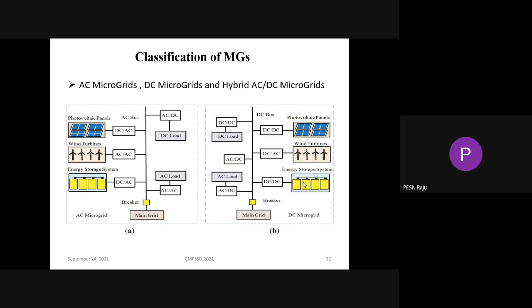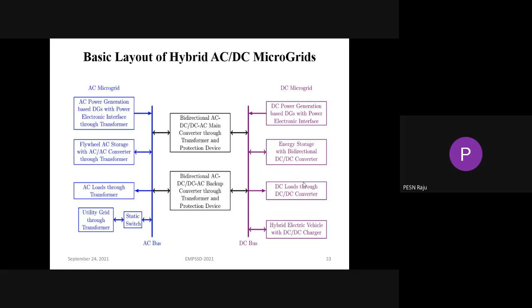So what we are doing is, the power generation which provides DC power is connected to the DC bus. Loads which require DC power, DC voltage, are connected to the DC bus, and likewise generation and loads which need AC power are connected to the AC bus. In between, we will have the bidirectional AC/DC converter. We have a main as well as a backup converter. So when there is a failure in the main converter, we can still operate with the backup converter, in order to improve the reliability and power supply to the critical loads.